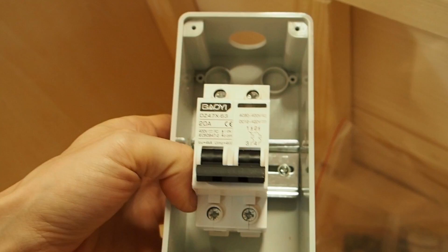Next we need a solar disconnect, which I have in this box here. This has 20 amps, so it should do fine for the solar panels, which have around 14 amps. You can connect two in series and the amps will stay the same, so this 20 amp breaker should be good for the solar panels. If it's breaking too early, we can always switch this out with a stronger one.